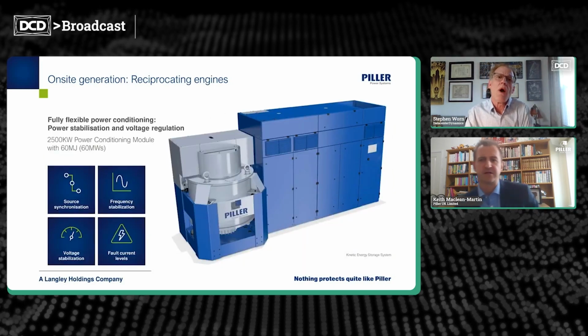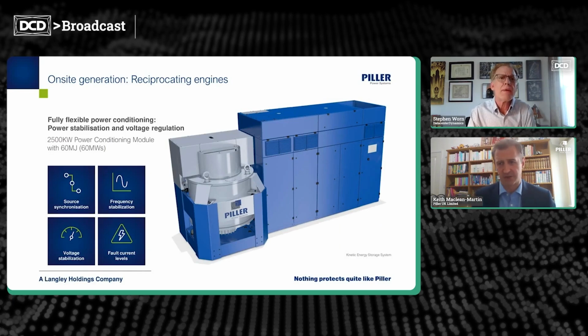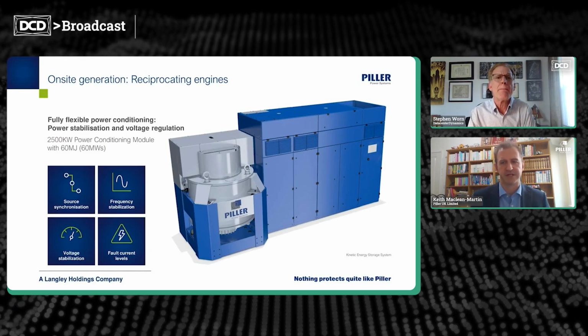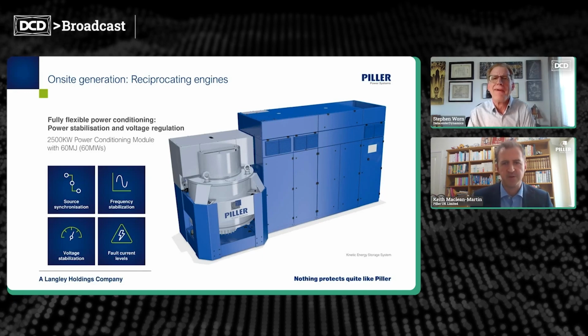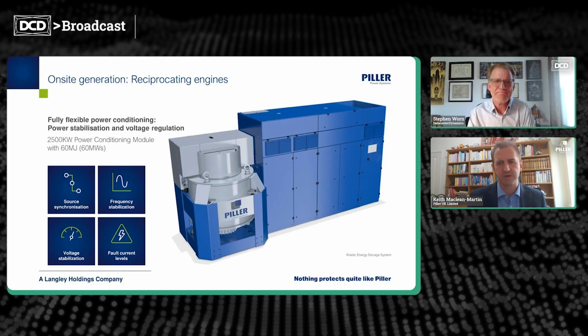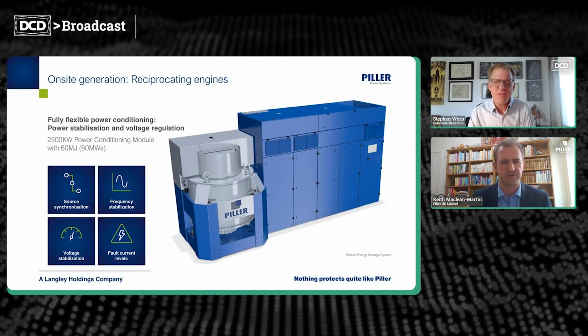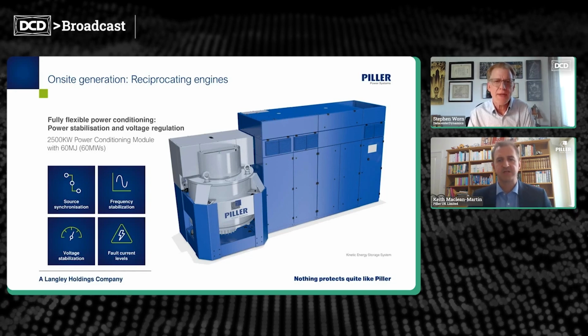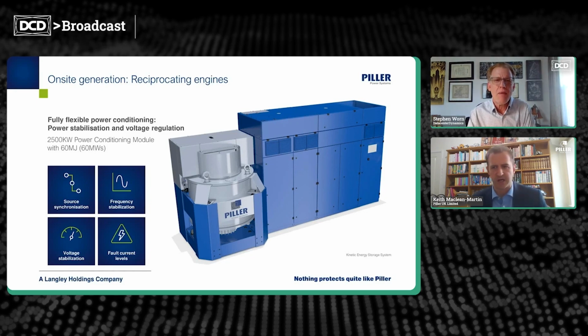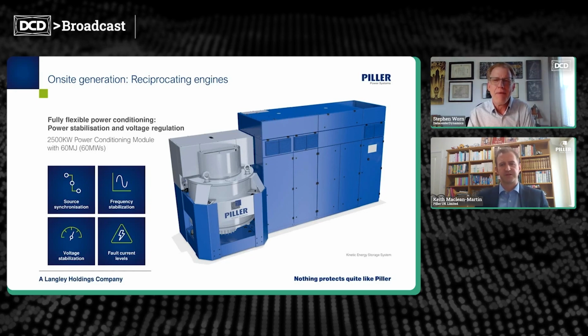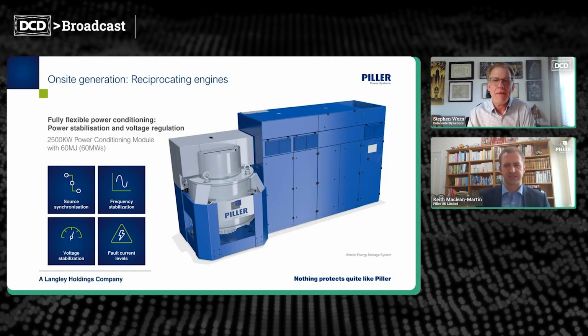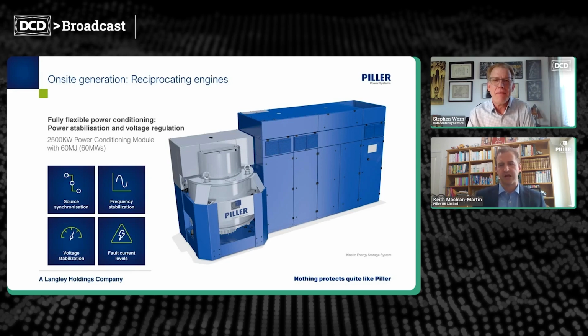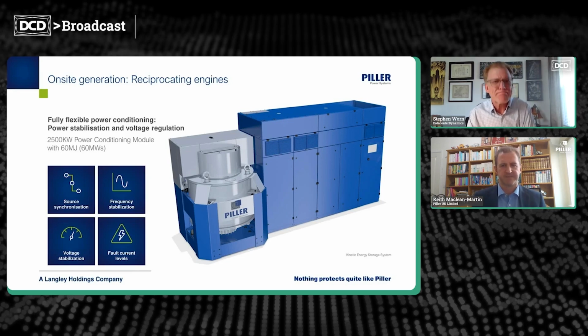The integrated power conditioning and switching technology is coupled to the primary on-site power generation and any other renewable sources as well. Here we see a Piller 2.5 megawatt power conditioning module with a 60 megajoule kinetic energy store. So conditioned power can be distributed as required and scaled to the modular on-site power generation scheme, and the two schemes don't have to match each other's capacity, in fact.